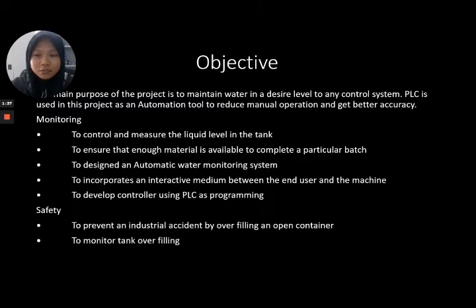Okay, for the objective, the main purpose of the project is to maintain the water at a desired level in any control system. PLC is used in this project as an automation tool to reduce manual operation and get better accuracy. Okay, we have two objectives. One is monitoring: to control and measure the liquid level in the tank to ensure that enough material is available to complete a particular batch, to design an automatic water monitoring system, to incorporate an interactive medium between the end user and the machine, and to develop a controller using PLC programming. The second one is for safety: to prevent an industrial accident by overfilling an open container, and to monitor tank overfilling.